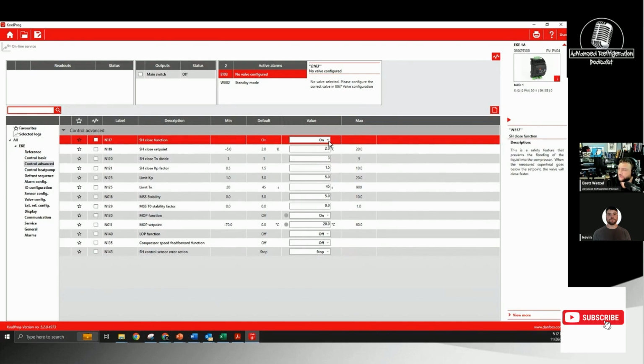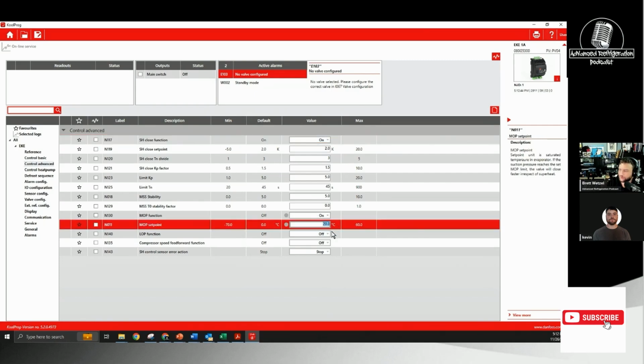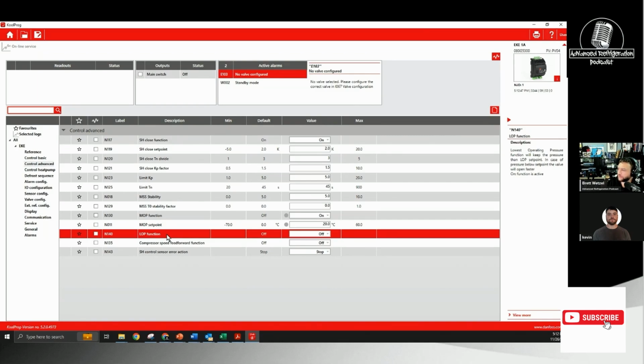Control advanced, superheat function, superheat close set point, superheat close TN divide, KP factor. So this is all like how to actually tune it to, I guess, where it's going to be more aggressive and less aggressive. You have the MOP function here. So using this for CO2, you could utilize that, or even on a regular conventional system if you're doing cases and you're trying not to take out your compressor. In this instance, it's set for 20 degrees Celsius. LOP, lowest operating pressure. So I guess you could have it stop. When would you have that do? Maybe if you lost a lot of gas and you don't want it to clamp down, so maybe you stop losing gas. Yeah, you could use it for that.